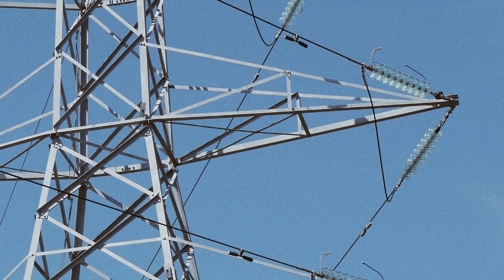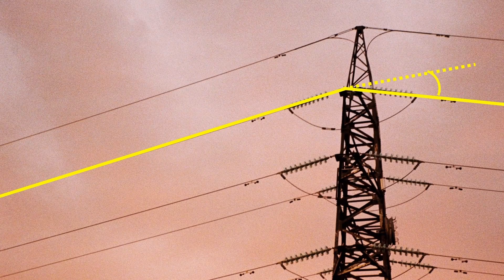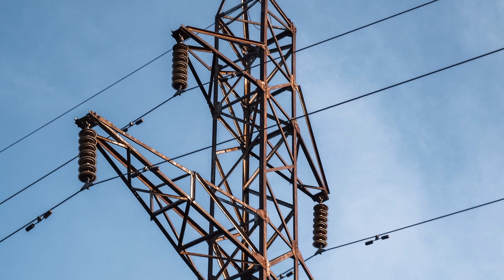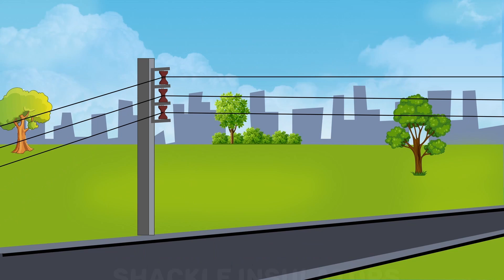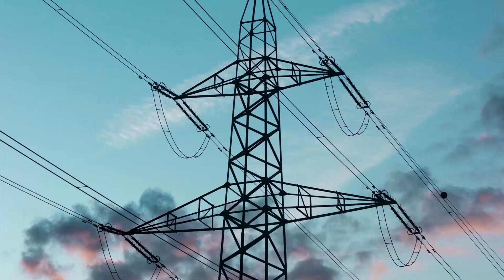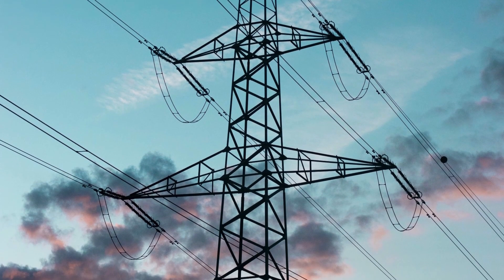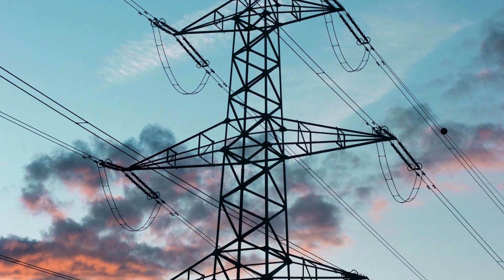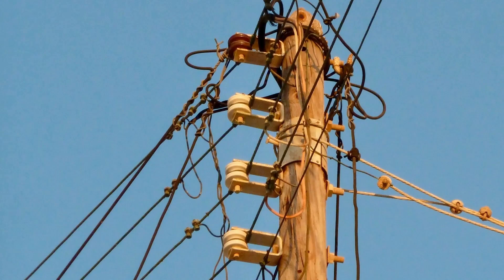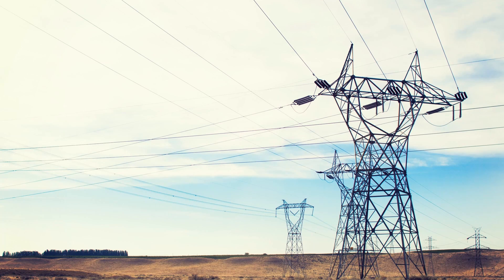Whenever the transmission line changes direction, we cannot use the suspension insulator. In such cases, either strain or shackle insulators are used. For high voltage lines, strain insulators are used, and for low voltage, shackle insulators are used. The discs of the strain insulators are arranged in a vertical plane. That's all for today. See you in my next video.